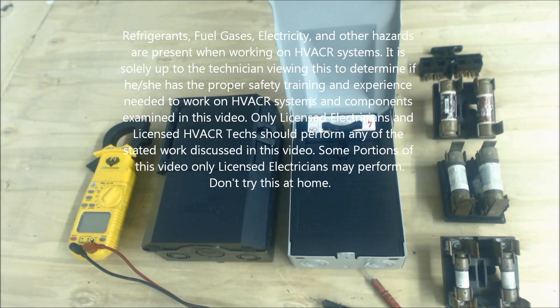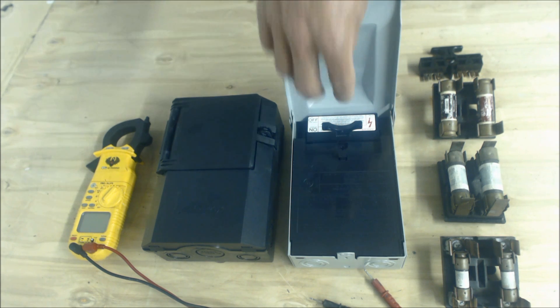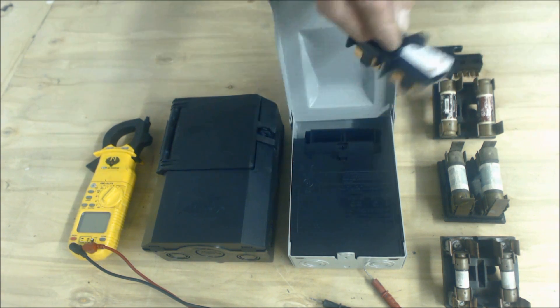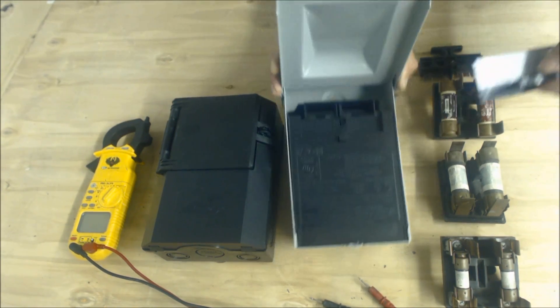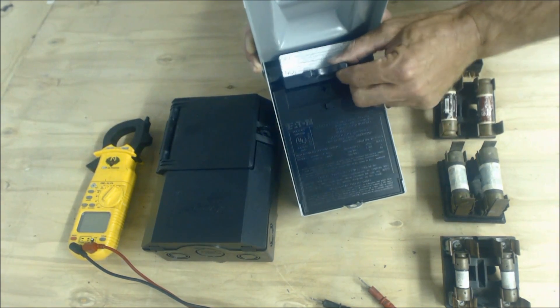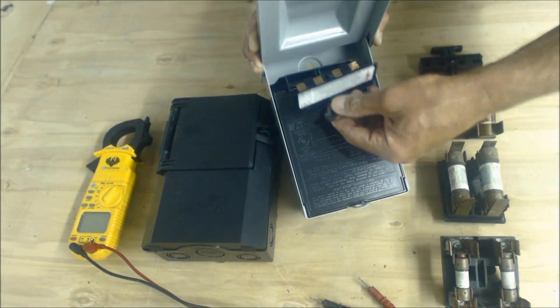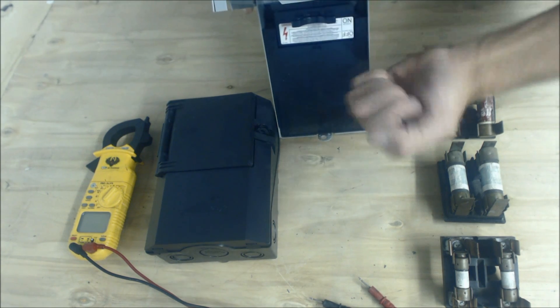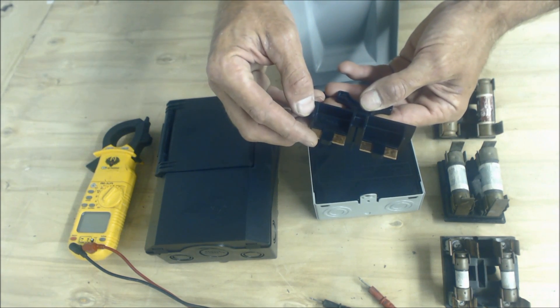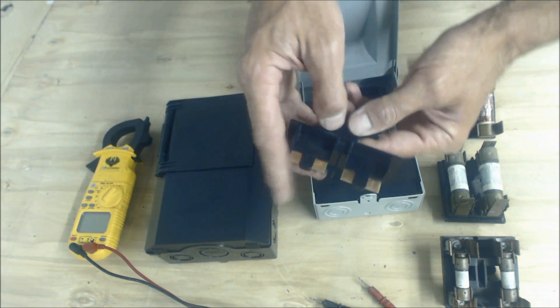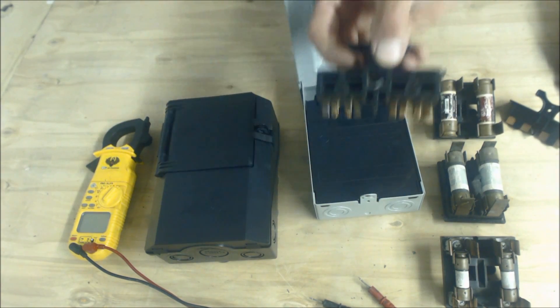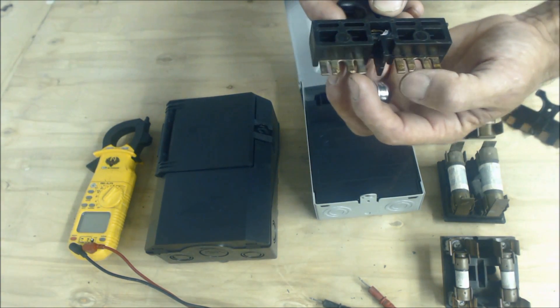A couple things I just want you to know is when you are servicing and pulling in and out the disconnects, what you should be doing is not putting them in all the way. So in this case it's off right now when you have this upside down, you're going to slide this in and then you're going to tap it in. It's important to not be touching the electrical connections and then not touching it and touching it again, and that's what's created on this one, burn marks.